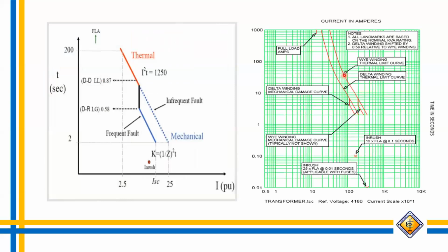Okay? So dapat pag nag-plot ka ng transformer, you should also consider the inrush current, 12 times the full load ampere at 0.1 seconds, as well as the inrush current of 25 times FLA at 0.01 seconds, which is applicable with fuses. Okay? Or fuse sizing.